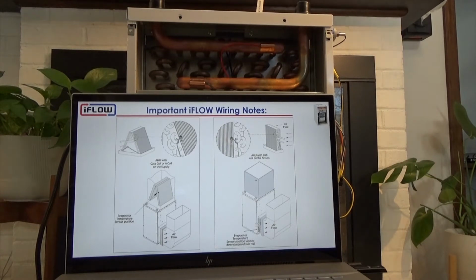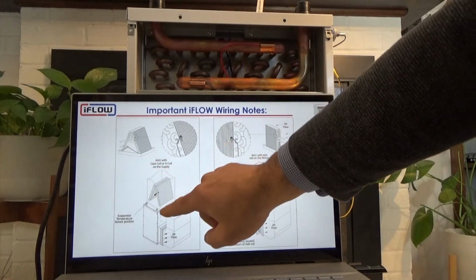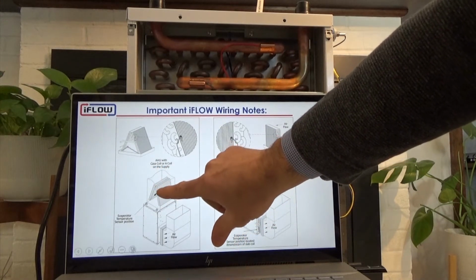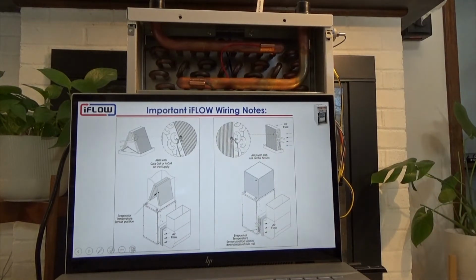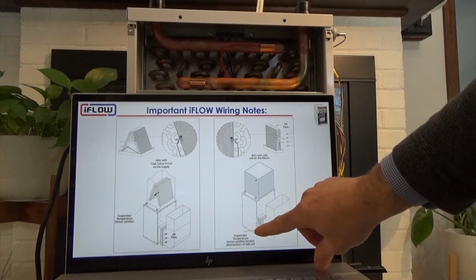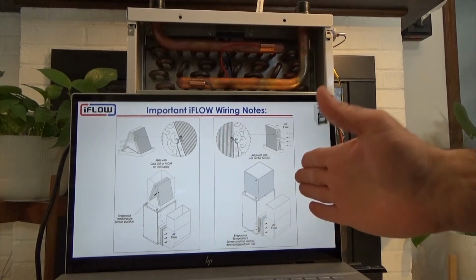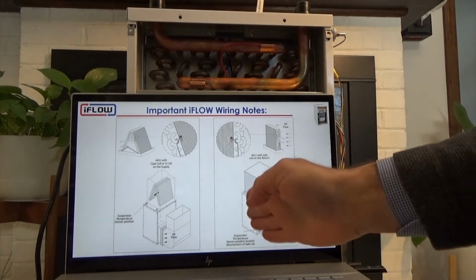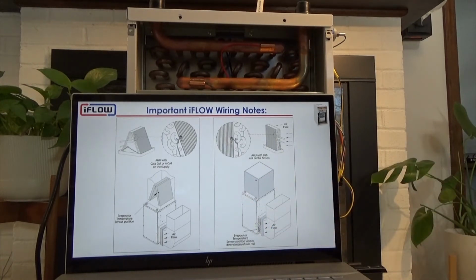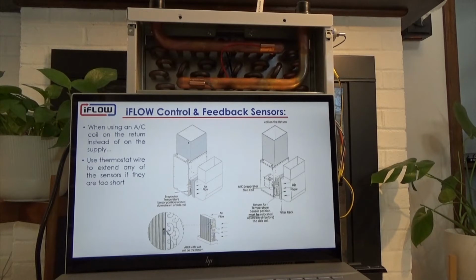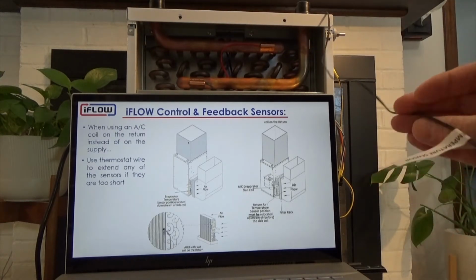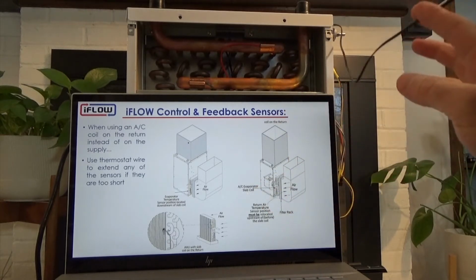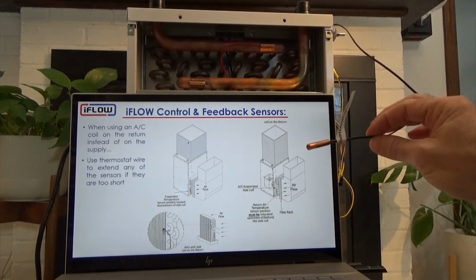So in terms of position of the evaporator temperature sensor, on an A coil on top, it will fit somewhere towards the top of the unit. If you're using a slab coil on the return, then it will be downstream of the coil, between the coil and the airflow, when you're using it on the return slab. If the wire harness is not long enough to reach when you're relocating it using a slab sensor, then you can use any thermostat wire to extend it without problem.